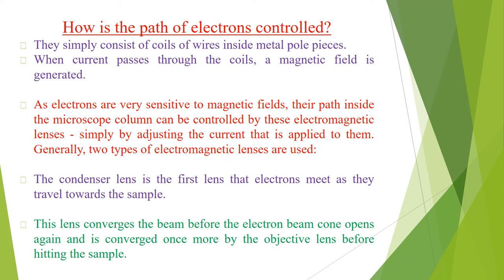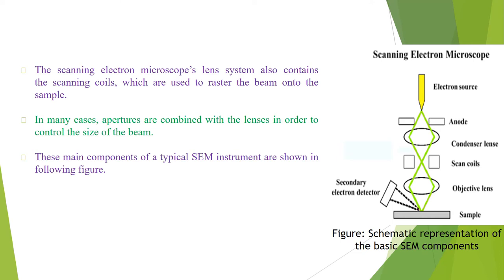By simply adjusting the current applied to the lenses, the electron path is controlled. Generally two types of electromagnetic lenses are used. Number one is the condenser lens, which is the first lens that electrons meet as they travel towards the sample. This lens converges the beam, which then opens again and is converged once more by the objective lens before hitting the sample. The condenser lens defines the size of the electron beam, which defines the resolution, while the main role of the objective lens is to focus the beam onto the sample.